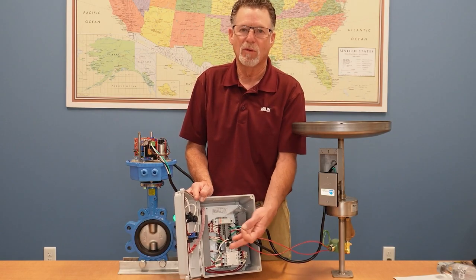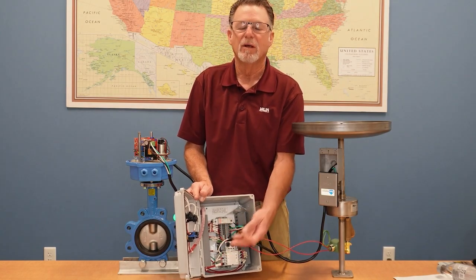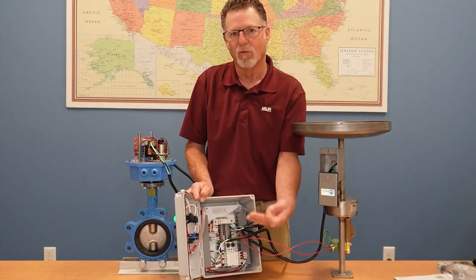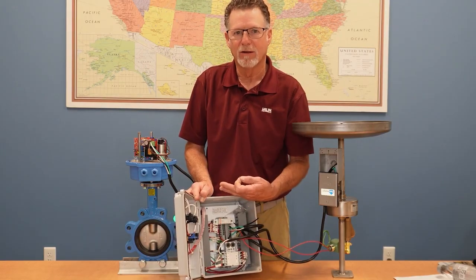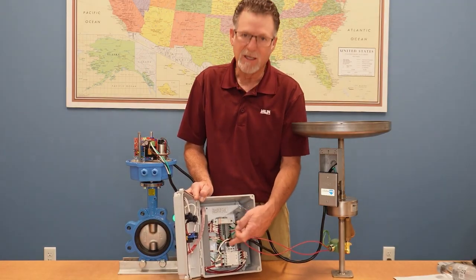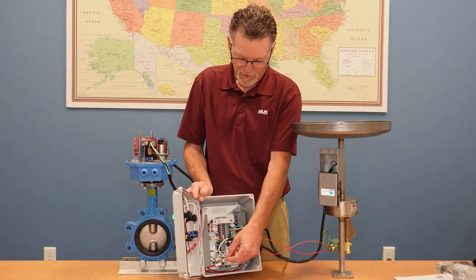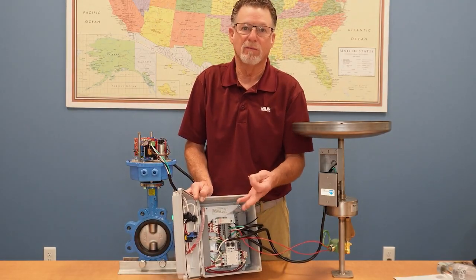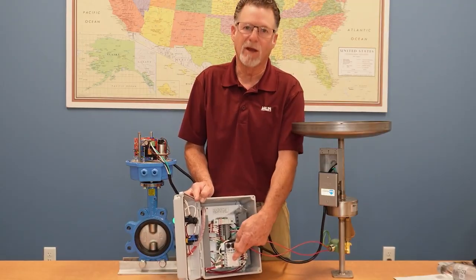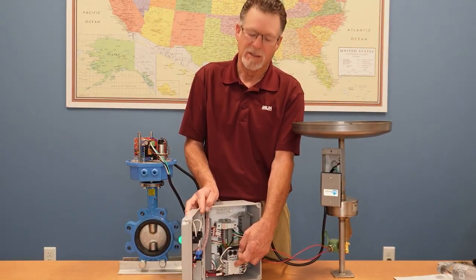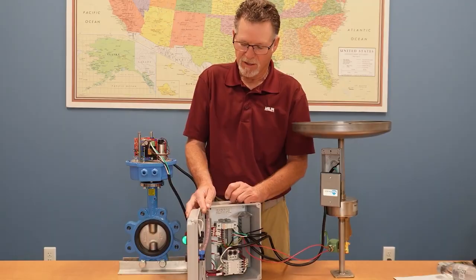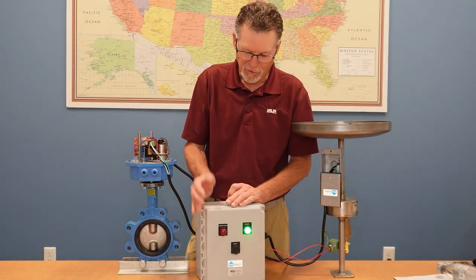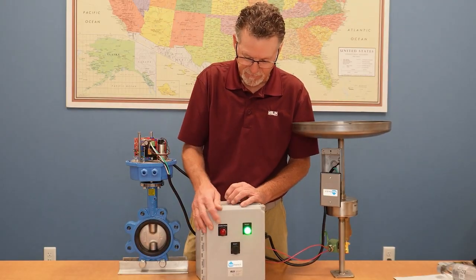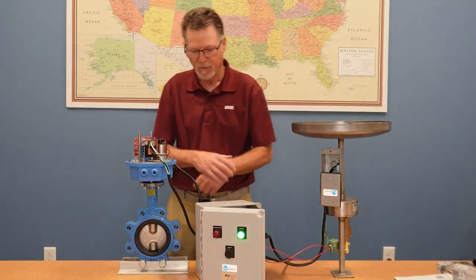It doesn't switch. So when you go to the divert condition, the 120 volts will go from terminal 8 to terminal 9. So that's an easy check with the voltmeter, and you just put this on there and, okay, the voltage didn't change, then you've got a bad relay. So that's another simple check of the pilot station. Other than that, you just have 2 lights. Pretty simple there. Push button.